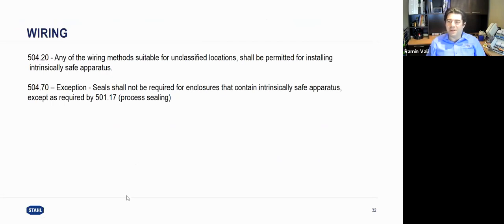One of the major advantages of having intrinsically safe is that we can use standard general purpose wiring, which we use for unclassified areas, also for classified areas. So that's a very good benefit of intrinsically safe signals. We don't need to have an extra wiring method like conduit or sealing or something like that. But at the same time, there are some other considerations when we are moving from one area classification to another. For example, if we go from zone 0 to zone 1, then we need to have a process sealing. But that's different from our protection method, because intrinsically safe protection doesn't need any sealing for transferring the signal.